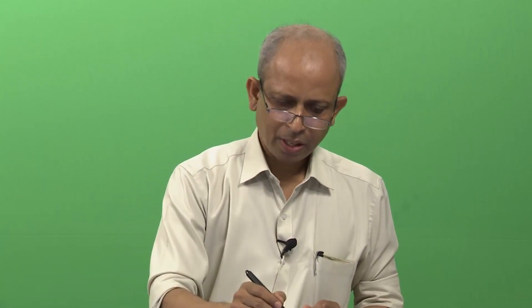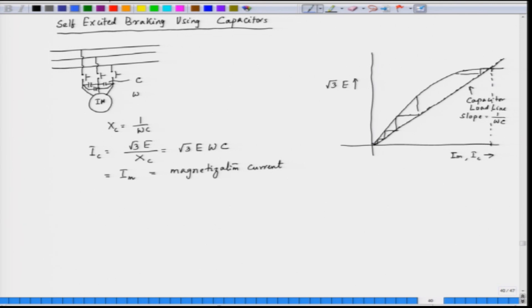When the motor speed comes down, the induced EMF also comes down. The frequency also comes down. Let us draw the magnetizing characteristic and the capacitance load line for a reduced frequency. If the frequency reduces, we will get a different magnetization characteristic — this is for a reduced value of frequency. The magnetization characteristic also reduces proportionately. So if f1 is the original frequency and f2 is the reduced frequency, then f2 is less than f1.